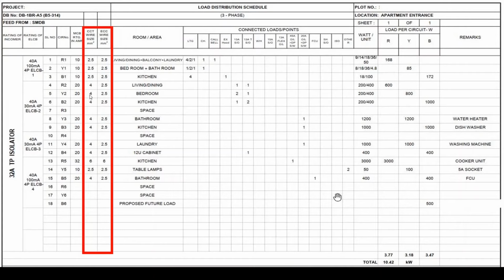So a typical power circuit, 20 amp, would have 4 mm wire for the phase circuit and 4 mm wire for the ECC circuit. Then in case I have a ring circuit, as we mentioned, which is a 32 amp breaker, that would have again 4 mm wire. That would be the only exception for the 4 mm wire. So if I have a ring circuit feeding from 6 to 10 sockets, I would put a 32 amp breaker and 4 mm wire.